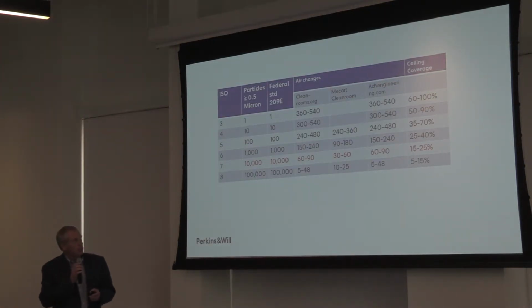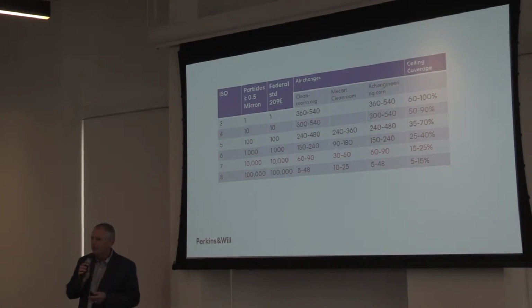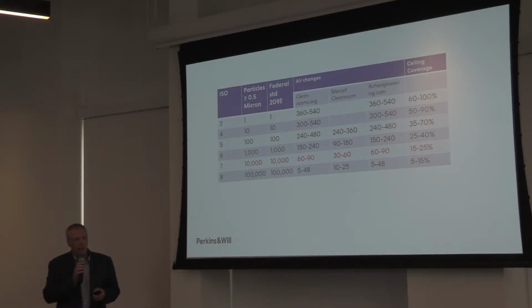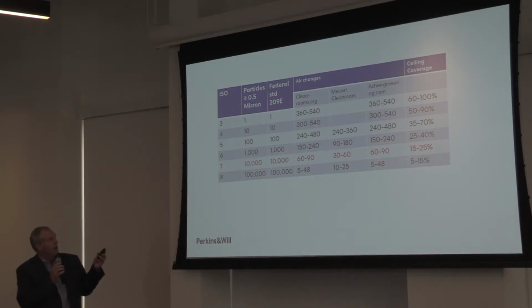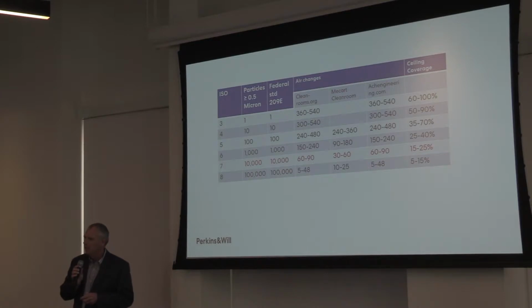With clean rooms, the answer is always it depends. The classification for clean rooms is based on how many particles of a certain size can be present within the space. We've morphed from a federal standard to an ISO standard, and they don't even match up across all different particle sizes, so it's kind of difficult to tell. ISO 7 is approximately the clean room we need at Fermi, which is 10,000 particles. Even within that, the air change requirements can be anywhere from 30 to 90 air changes per hour. That's a pretty broad range for how much air we need to put into these clean rooms.